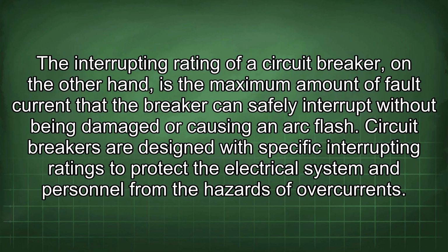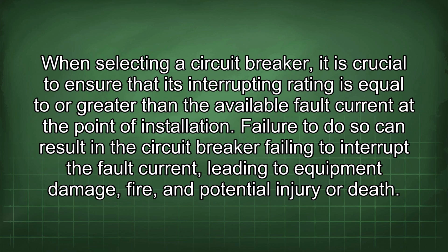Circuit breakers are designed with specific interrupting ratings to protect the electrical system and personnel from the hazards of overcurrents. When selecting a circuit breaker, it is crucial to ensure that its interrupting rating is equal to or greater than the available fault current at the point of installation. Failure to do so can result in the circuit breaker failing to interrupt the fault current, leading to equipment damage, fire, and potential injury or death.